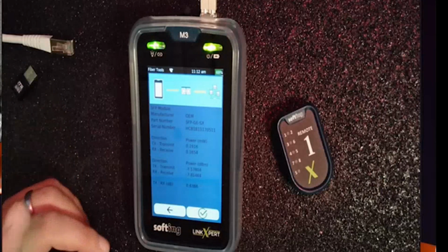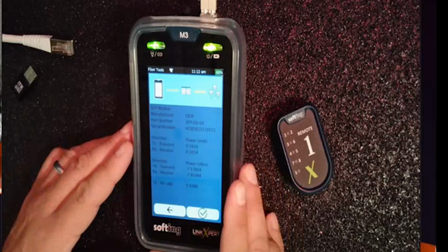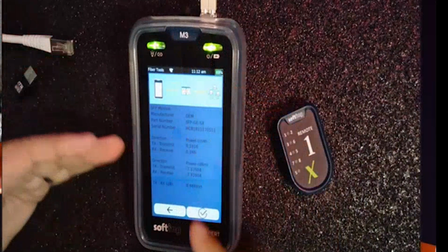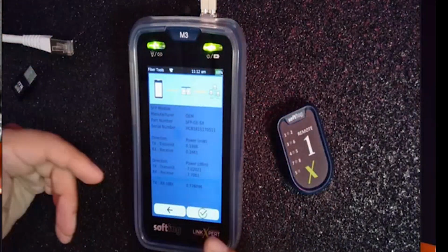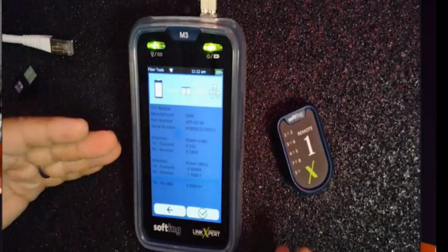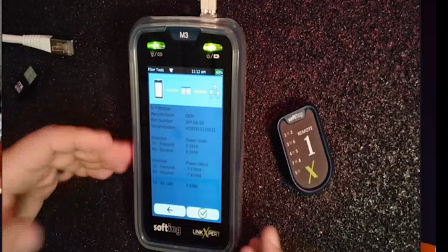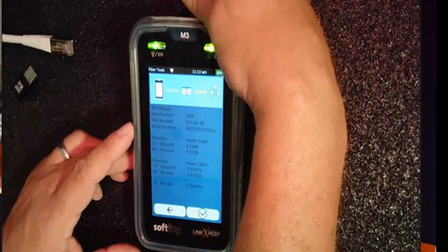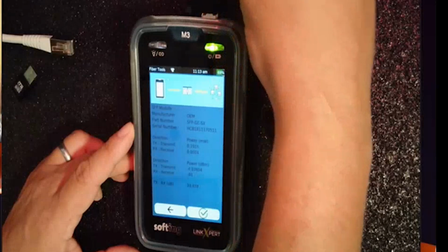You can use this in multiple scenarios. If you have another LinkXpert, you can be at the opposite side and do a dual-ended test. It would give you values for power and receive at both ends. So that's the TX-RX function on LinkXpert, very handy when it comes to fiber optic troubleshooting.